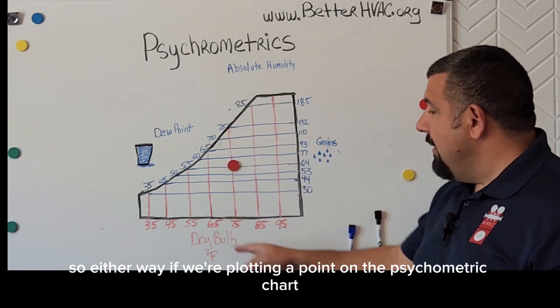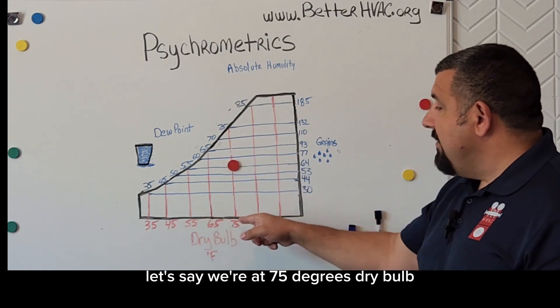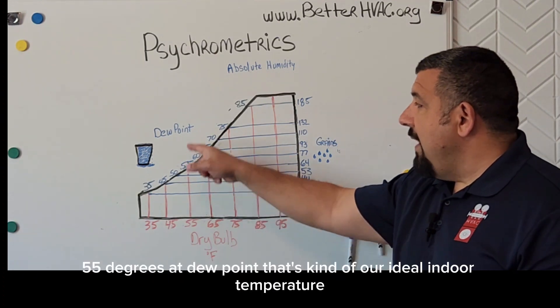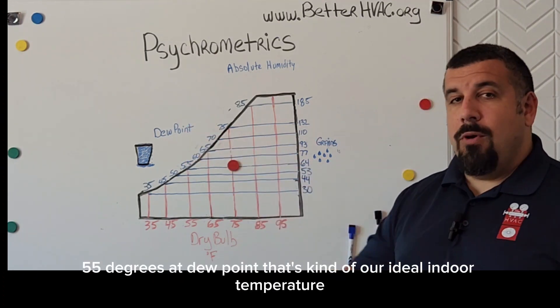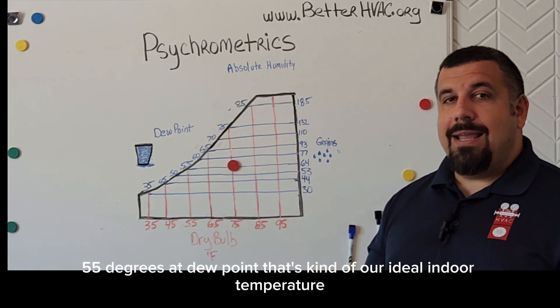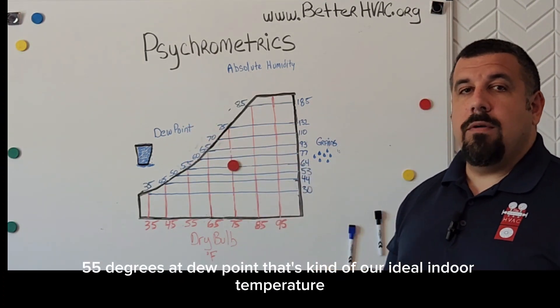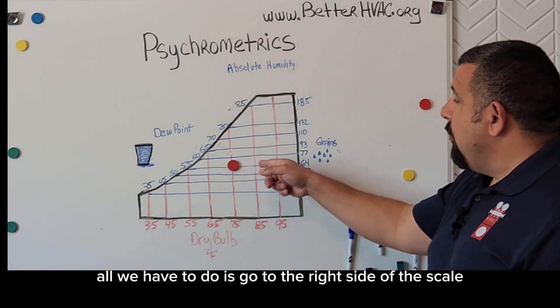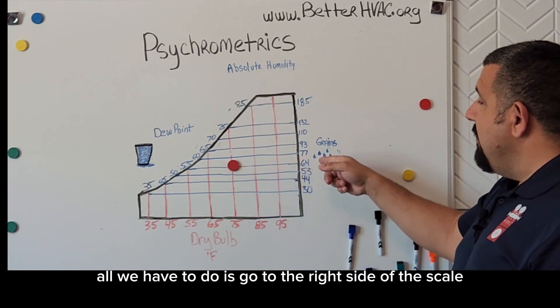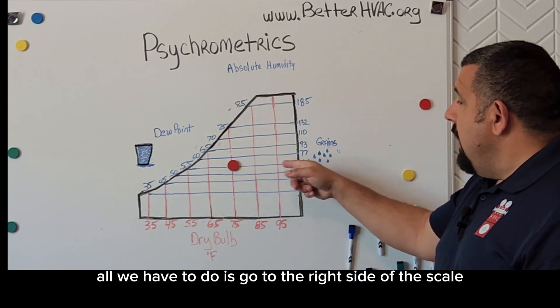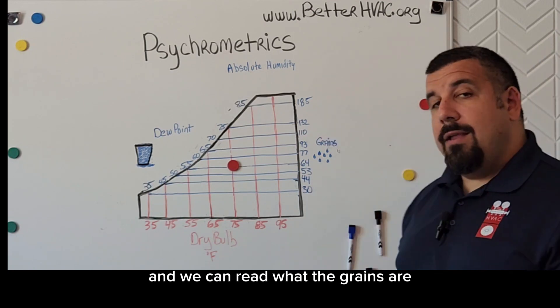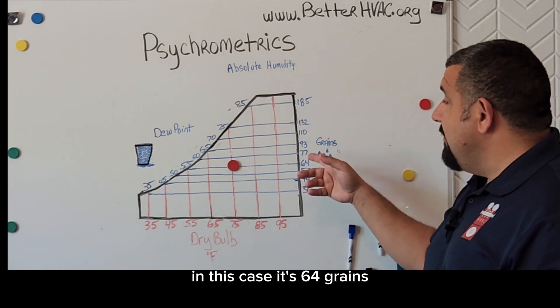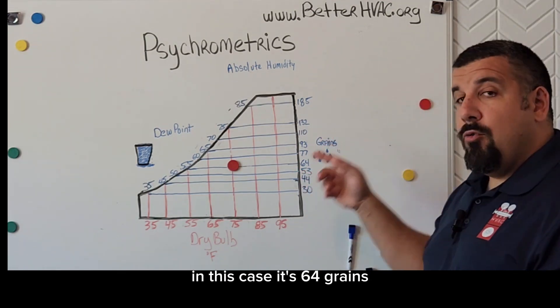That's the psychrometric chart. Let's say we're at 75 degrees dry bulb and 55 degrees dew point — that's kind of our ideal indoor temperature. All we have to do is go to the right side of the scale and we can read what the grains are. In this case, it's 64 grains.